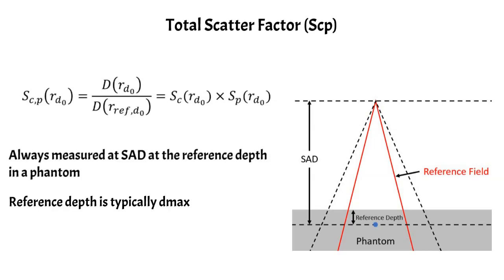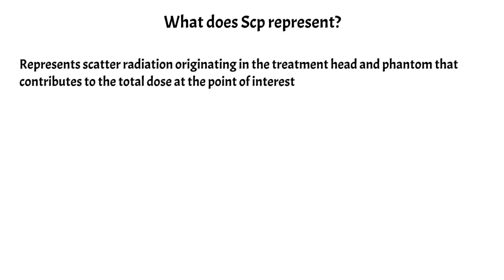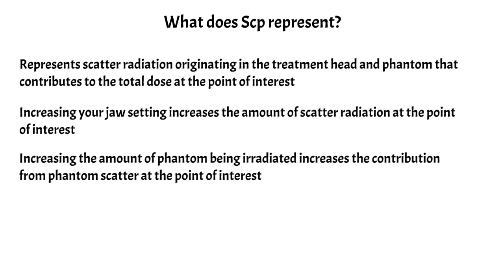A couple of notes about the reference depth: typically it is taken to be D max, though it doesn't necessarily have to be. As the name suggests, the total scatter factor represents the total scatter contributing to the dose at the point of interest — scatter can come from the treatment head and from the phantom. As we increase jaw setting, it makes intuitive sense that more scatter from the collimators can get through and more scatter radiation is created in the phantom, giving a greater contribution at the point of interest.